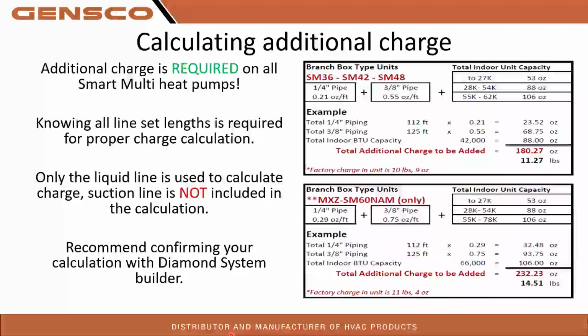Calculating additional charge. All smart multi heat pumps, you have to add charge to them. We get this call on the tech line for performance problems on smart multi fairly often, and one of the first questions I ask is how much charge did you add to the system? A lot of times guys will tell me, oh, we didn't add any charge because we're under the 400-foot max that it says we're allowed. Unfortunately, they are misunderstanding the instructions. With the smart multi systems, the heat pump only comes with enough charge in it for itself. So any amount of line set you add, you'll have to add charge for. You'll have to add additional charge for all of your indoor coil capacity as well.